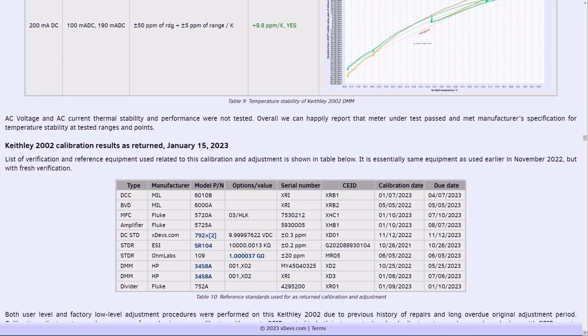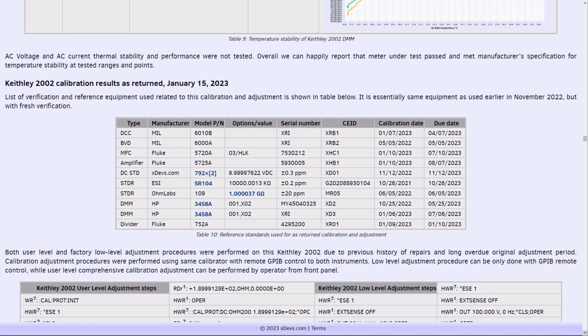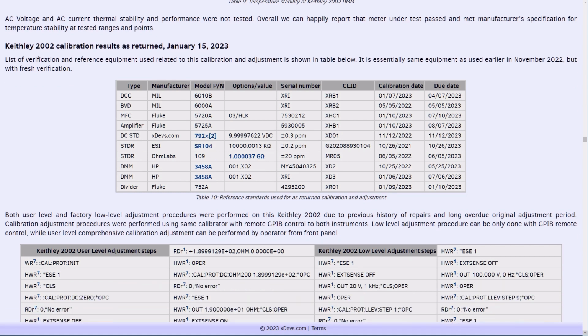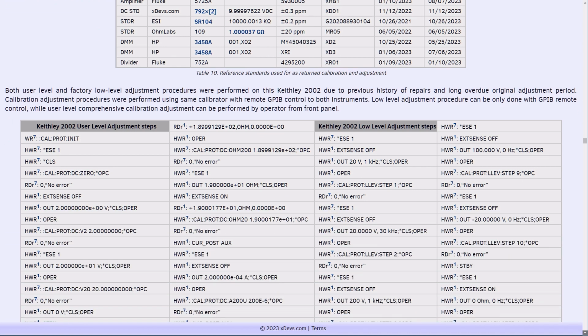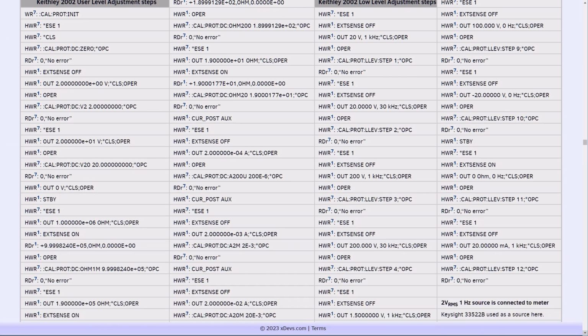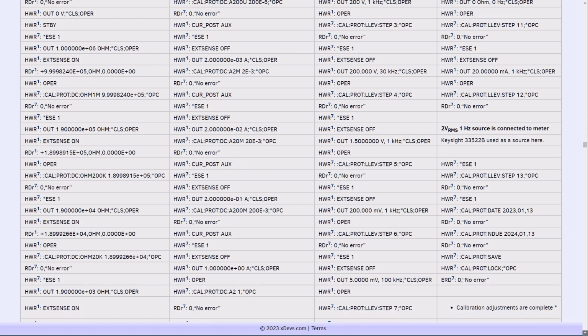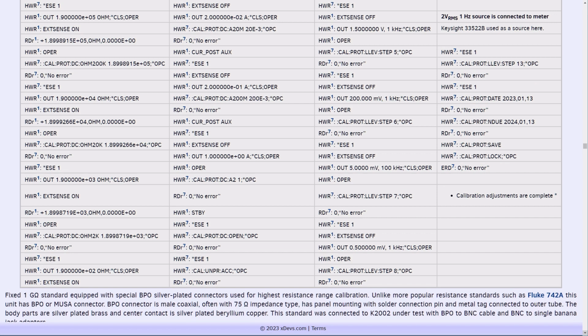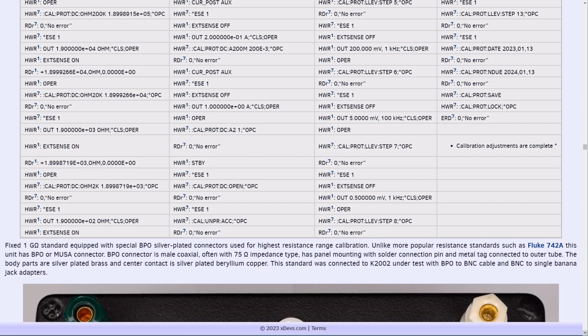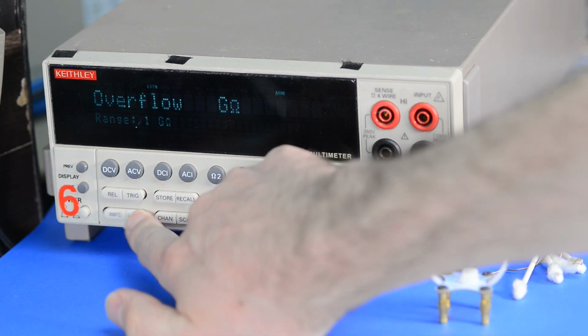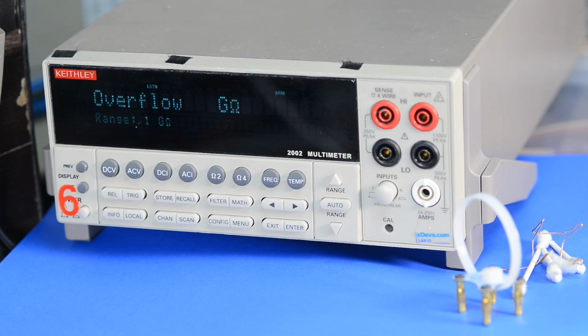And at this point we can do the full adjustment for this instrument using the calibrator. And in table 11, you can see commands used to send to calibrator and DMM during the adjustment procedure protocol. These adjustments were done on January 13, 2023 with a freshly adjusted and tested calibrator. To start calibration, need to poke a hidden button Cal under the input switch, and this will allow instrument to accept calibration constants after the fresh adjustment procedure.